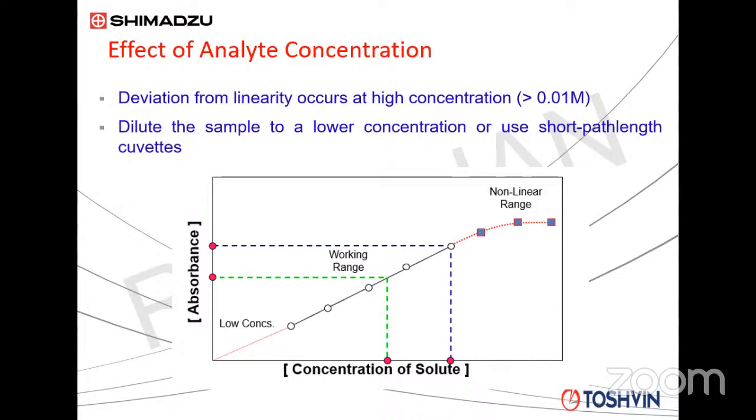In the linear range, you can see, I have prepared a 5-point calibration here. You can see 5 different concentrations we prepared, and all the absorbance values are falling in a straight line, and that is the linear range. That is the working range of my equipment. So your measurement should be in the linear range.